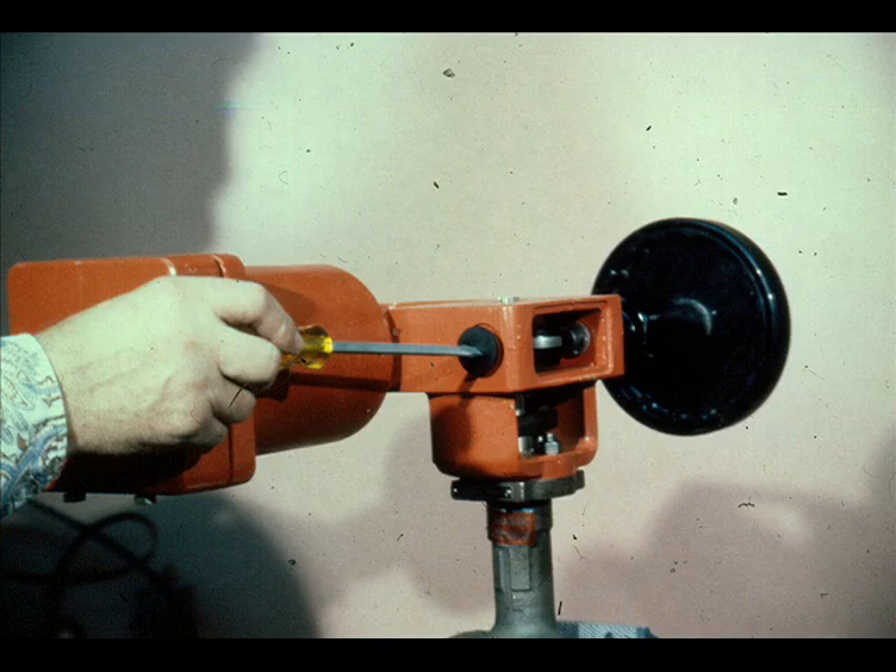Replace the handwheel washer and Truarc ring and back off the handwheel so it will not interfere with the operation of the lever. Replace the handwheel thread plug. If the valve is equipped with the optional limit stop instead of the thread plug, it must now be installed. Back off the stop so it will not interfere with operation of the lever at this time.